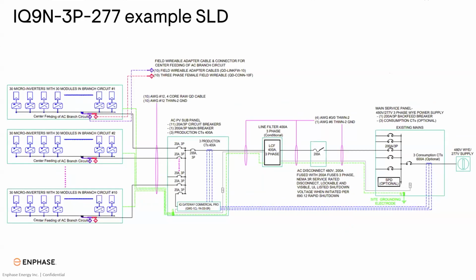So let's take a look at an example single line diagram. This is an example one that we have on our website for anybody to utilize and look at to help build their own. In this example, we'll start on the left-hand side. We have our micros and our panels. This one is as simple as it gets. We have 30 micros per circuit, and we have 10 circuits. So that gives us 300 micros, which is the maximum number of micros that a gateway can communicate with.